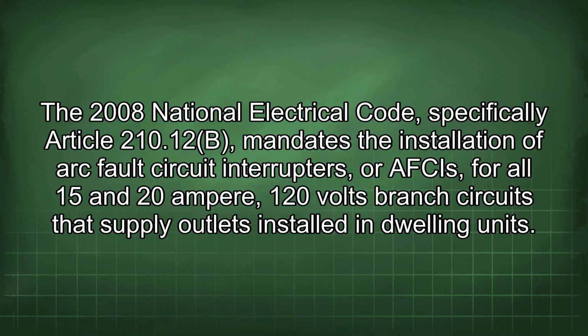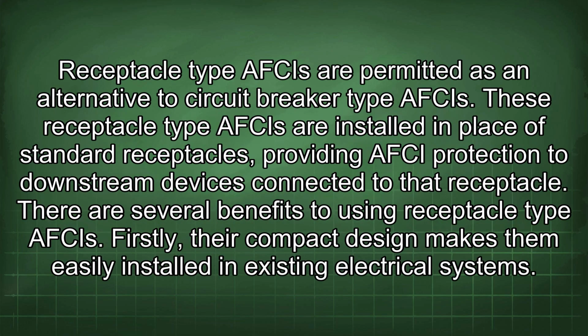The 2008 National Electrical Code, specifically Article 210.12(B), mandates the installation of arc fault circuit interrupters, or AFCIs, for all 15 and 20 ampere, 120 volt branch circuits that supply outlets installed in dwelling units. Receptacle type AFCIs are permitted as an alternative to circuit breaker type AFCIs. These receptacle type AFCIs are installed in place of standard receptacles, providing AFCI protection to downstream devices connected to that receptacle.